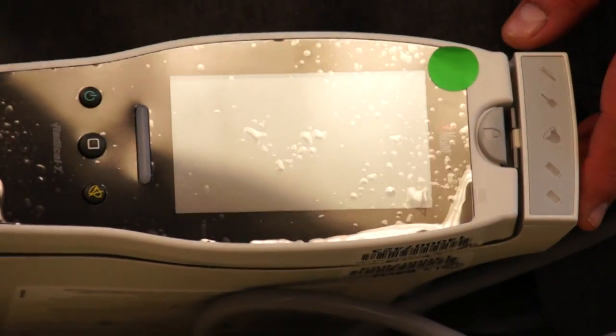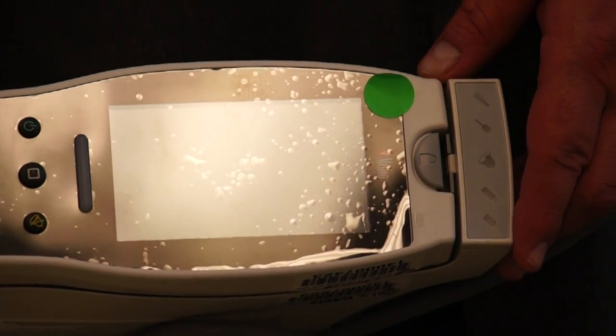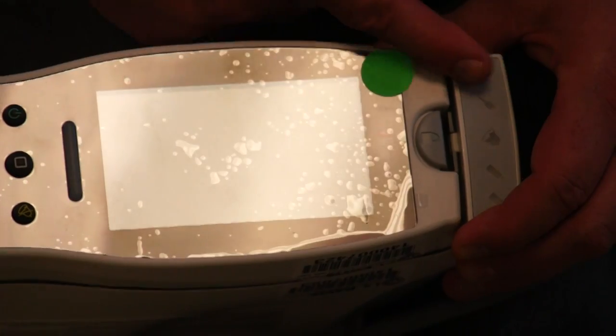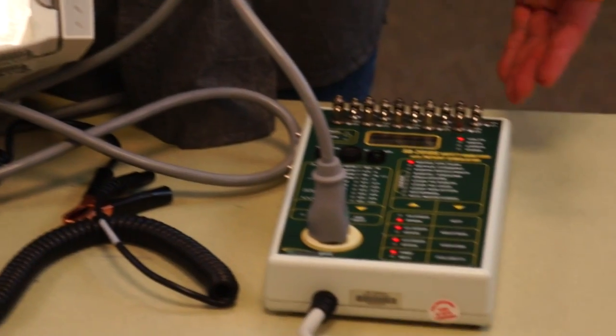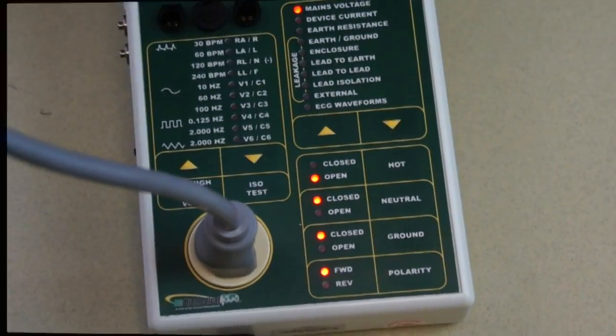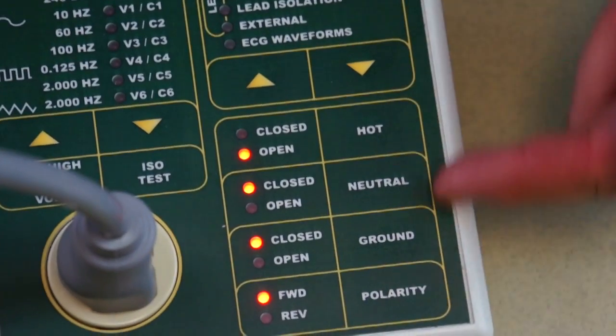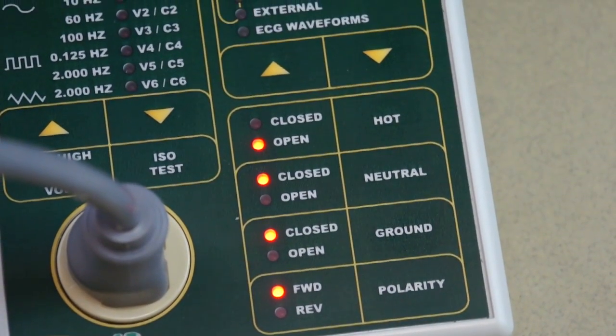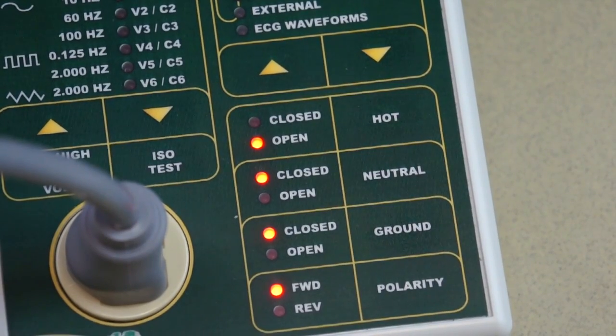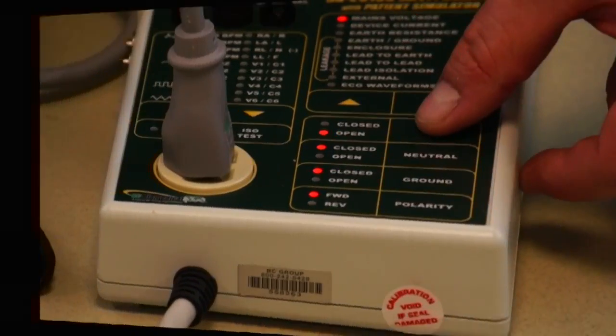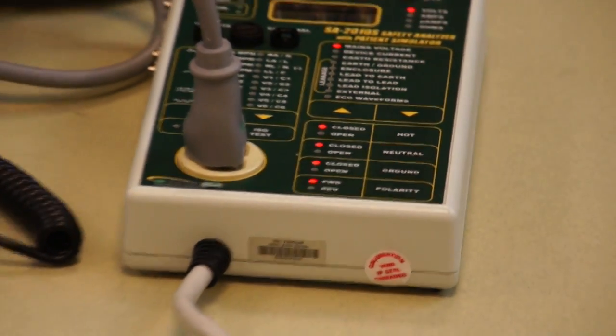You will notice that although we have the device under test plugged in, we are not getting any power to that device. The reason for that is when the analyzer powers up, for safety, it puts the hot wire on the test receptacle into an open state, and no power is going to the device under test. If we close the hot wire, we will notice now that the device under test will start to power up.